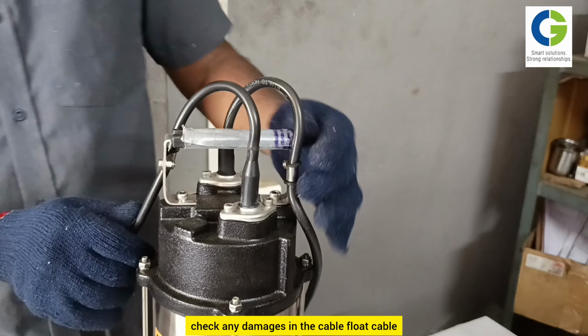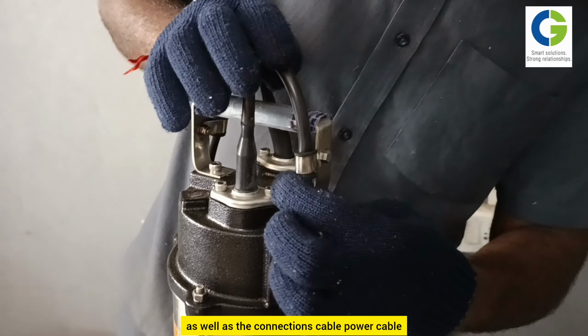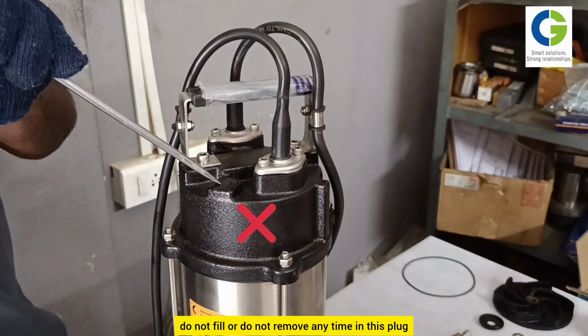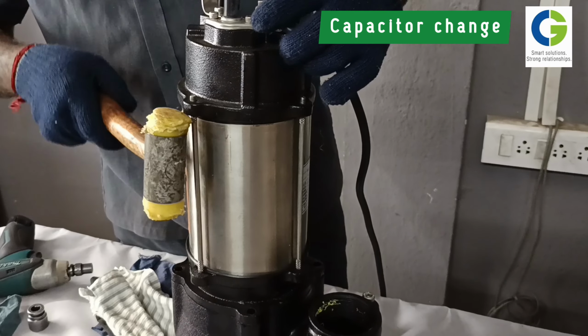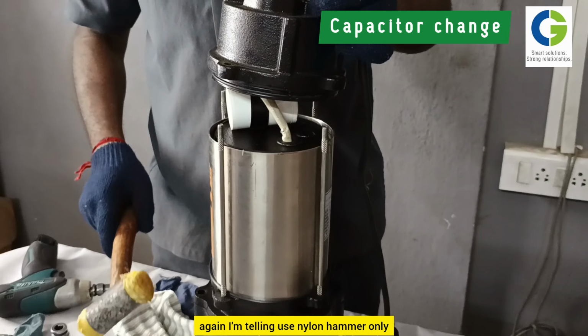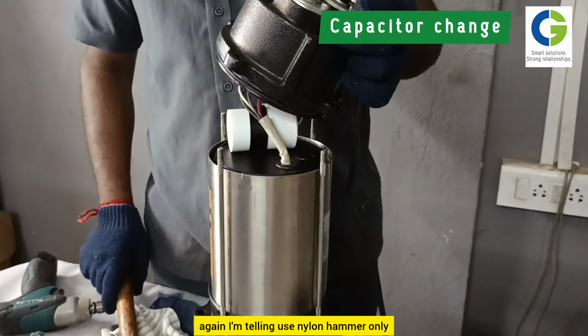Check for any damage in the cable, the float cable, as well as the connection cable and power cable. Do not fill or remove anything at this plug any time. Remove the top cover, and now we'll see how we can replace the capacitor. Again I am telling you, use a nylon hammer only. Here the capacitor is mounted inside the top cover. Cut the extension cable and replace it with a new capacitor. You can use this clamp for mounting.